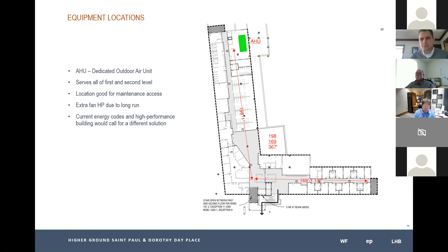We tried to apply it at Dorothy Day, and I'll show you a slide later on about that. This is an image of the configuration at Higher Ground, which is one fan coil unit that serves 3 SRO units. It replicates what they did at Higher Ground Minneapolis. Fresh air comes into that center unit as well as exhaust, and then that fan coil serves all 3 rooms. Had we been able to predict COVID was going to happen in 2020, we probably wouldn't have set it up this way.